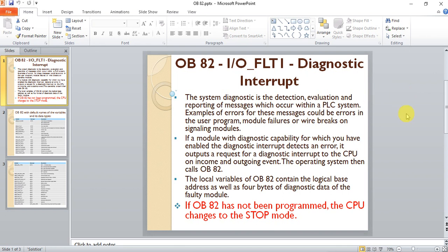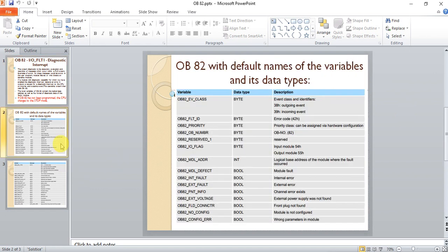If OB82 has not been programmed, the CPU changes to stop mode. OB82 has many default variables that provide information about the error and the current status of the CPU. We can extract hardware messages to our PLC program by using those variables, which we will see later in this video.